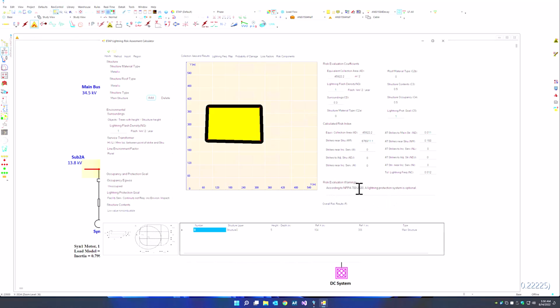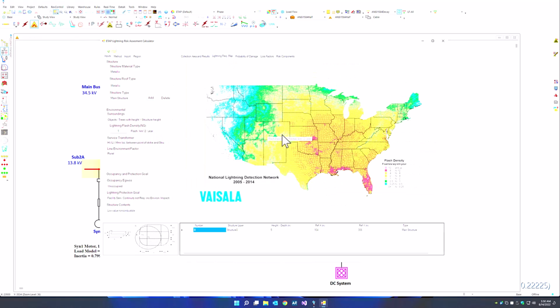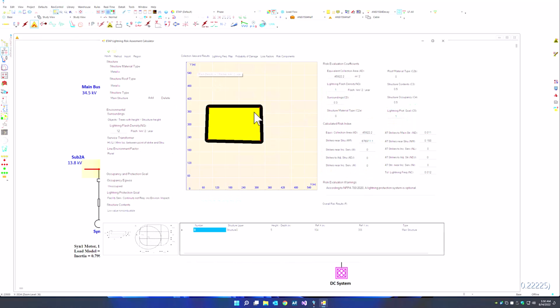And according to NFPA 780, a lightning protection system is optional in this particular case with a lightning flash density of 1 flash per kilometer square per year. We can of course go to our lightning frequency map. We can pick from a different lightning density such as 12 flashes, which is updated within our calculator. Go back to our simulation and you can see the protection system is still optional.